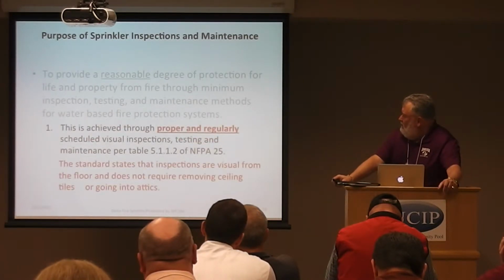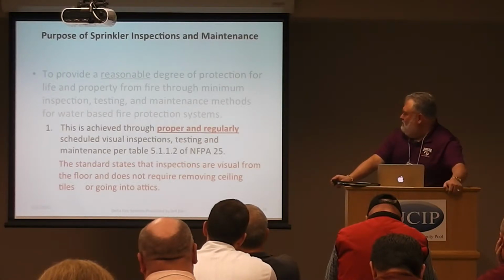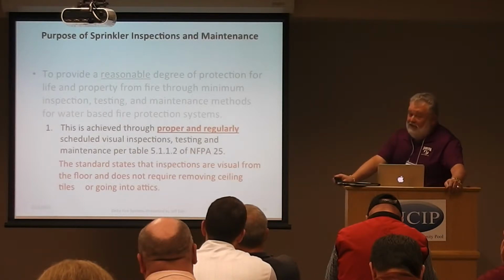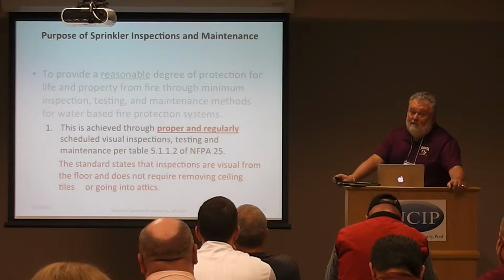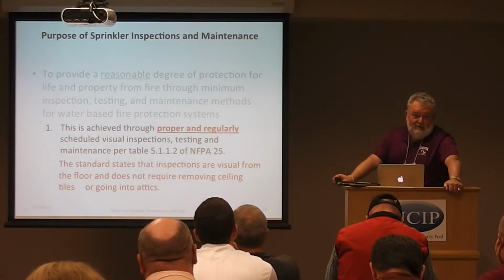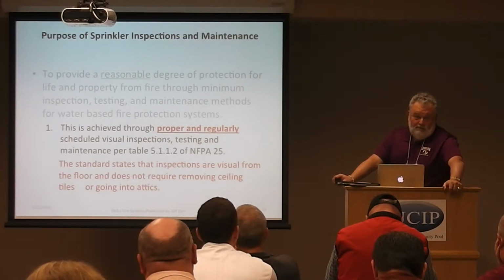All right, and they go on to say the reasonable degree is achieved through proper and regularly scheduled visual inspections, testing and maintenance per table 5.1.12 of 25. The standard states that those inspections are visual from the floor, and they don't require removing ceiling tiles or going into the attic. Some inspectors actually in big, higher facilities will carry binoculars with them. That way they can look up and see sprinkler heads, see if there's corrosion on them, see if there's anything with hangers or something that would indicate a possible problem.